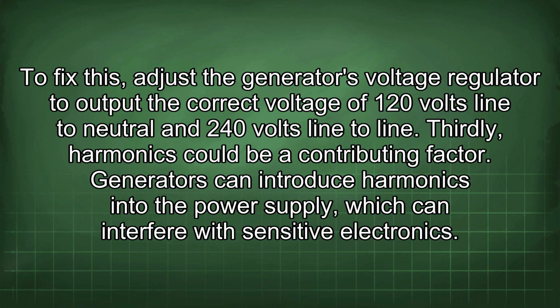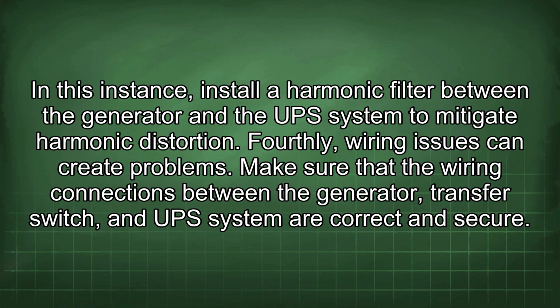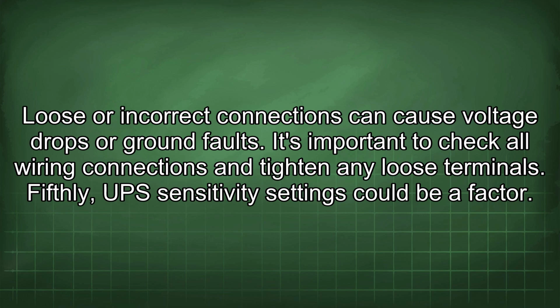Thirdly, harmonics could be a contributing factor. Generators can introduce harmonics into the power supply, which can interfere with sensitive electronics. In this instance, install a harmonic filter between the generator and the UPS system to mitigate harmonic distortion. Fourthly, wiring issues can create problems. Make sure that the wiring connections between the generator, transfer switch, and UPS system are correct and secure. Loose or incorrect connections can cause voltage drops or ground faults. It's important to check all wiring connections and tighten any loose terminals.